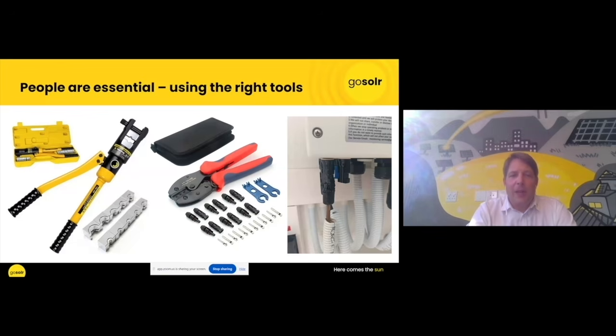The one in the middle is used for crimping MC4s. MC4s are used to link DC cables from the inverter to the panels, or going into the inverter. Again, if you use pliers you might do it wrong, the tension might be off, and you end up with something loose, which can lead to the type of issues you see on the screen, where the MC4 heated up and started melting.